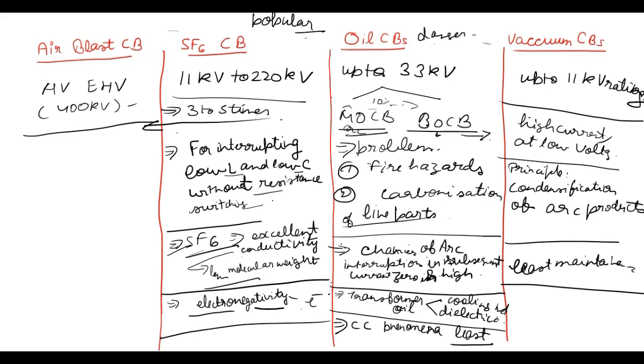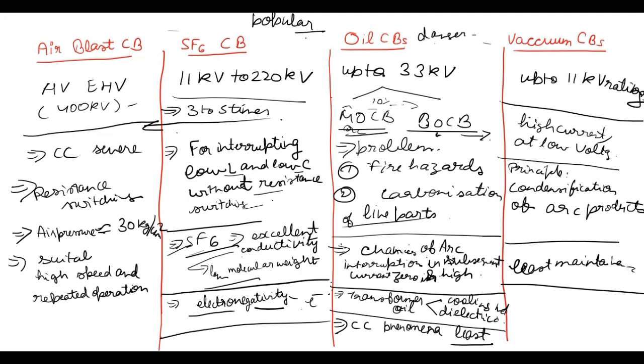Now air blast circuit breakers. So here CC phenomena is very severe. Here mainly resistance switching is used. Here air pressure is around 30 kilogram per centimeter square. It is suitable for high speed and repeated operation.